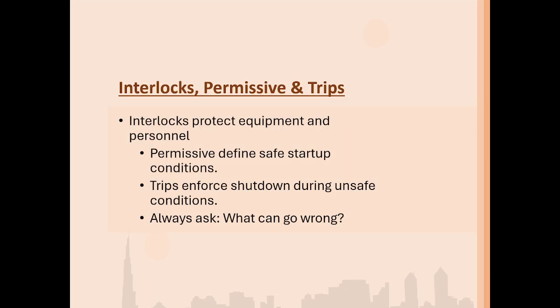Now let's define these terms clearly. What is an interlock? An interlock prevents an action unless certain conditions are safe. A permissive is a condition that must be true before equipment is allowed to start. A trip forces equipment to shut down when unsafe conditions occur. Good automation engineers always ask one question while designing logic: what can go wrong? That's always the question a good automation engineer will ask. And that question leads directly to fail-safe design.